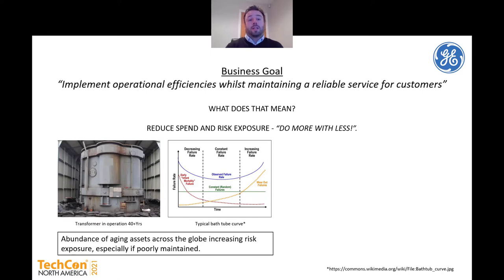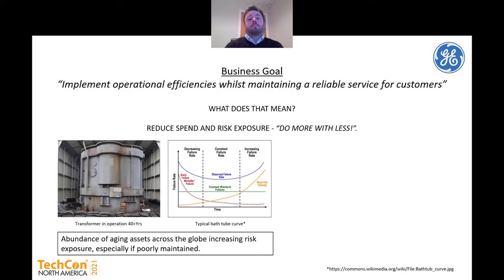You can see in the two images on the slide — the one on the left is a transformer that's been in operation for 40-plus years. This transformer is operating and doing what it's supposed to, but at this point it is well beyond its designed life. That is a common theme in many utilities where assets are still operating today and playing a crucial role in the grid well beyond their design life. You can also see a typical bathtub curve for assets, which shows an increased risk of failure at the very early stages of the asset's life, then stabilizes, and then starts to increase again as the asset gets older and components start to wear.